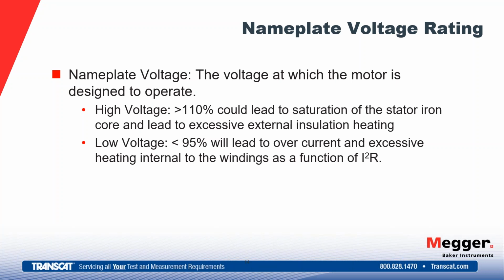Too high a voltage can lead to saturation of the iron core and leads to excessive heating from the inside out. So as we apply more voltage than what the field is designed for, as we apply voltage to that motor, we get that rotating magnetic field. The strength of that magnetic field is directly related to the voltage that we're applying to it. And if we're applying more voltage than is needed, at some point we will saturate the iron core, causing eddy currents and hysteresis losses in the iron core, which cause heating.